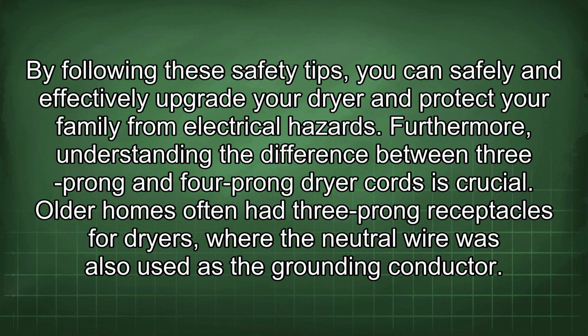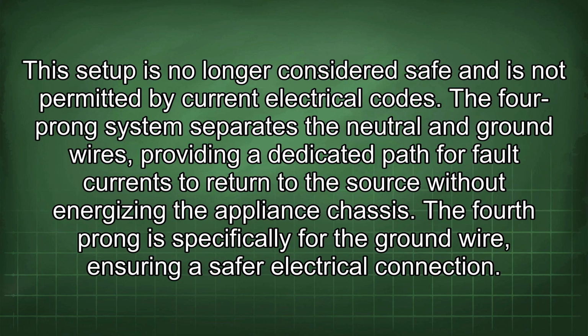Furthermore, understanding the difference between three-prong and four-prong dryer cords is crucial. Older homes often had three-prong receptacles for dryers, where the neutral wire was also used as the grounding conductor. This setup is no longer considered safe and is not permitted by current electrical codes. The four-prong system separates the neutral and ground wires, providing a dedicated path for fault currents to return to the source without energizing the appliance chassis. The fourth prong is specifically for the ground wire, ensuring a safer electrical connection.